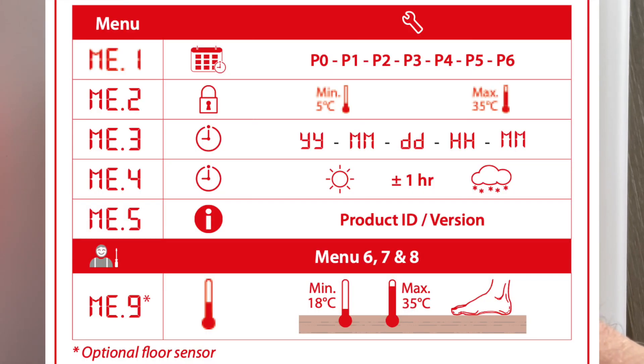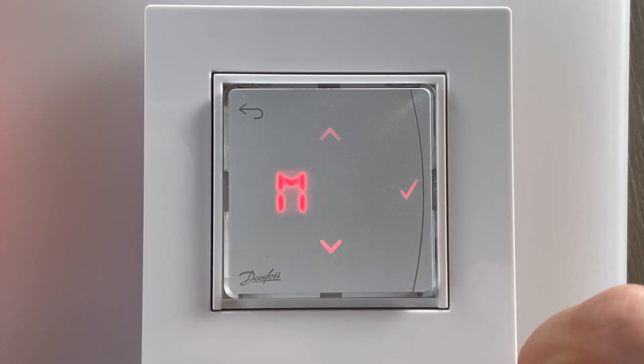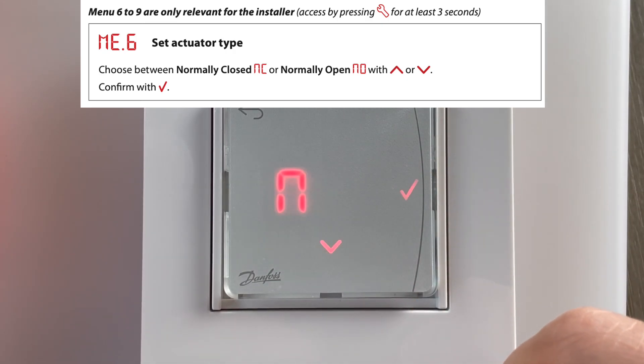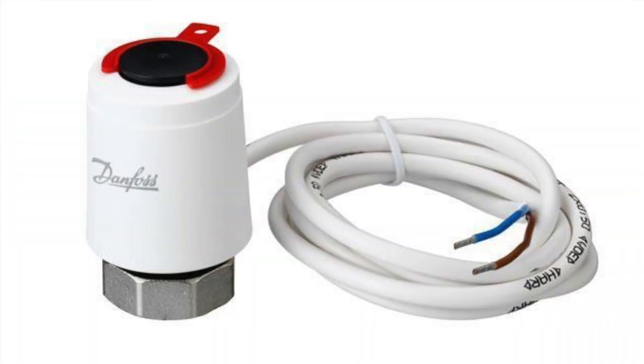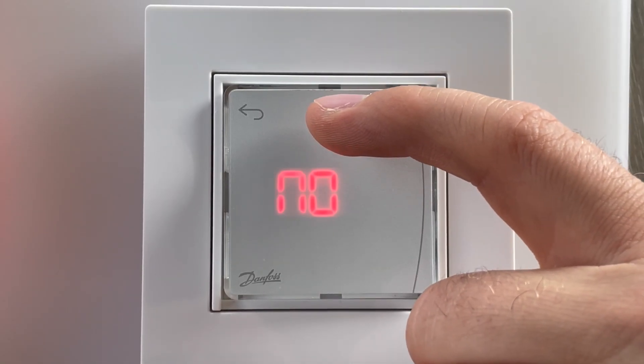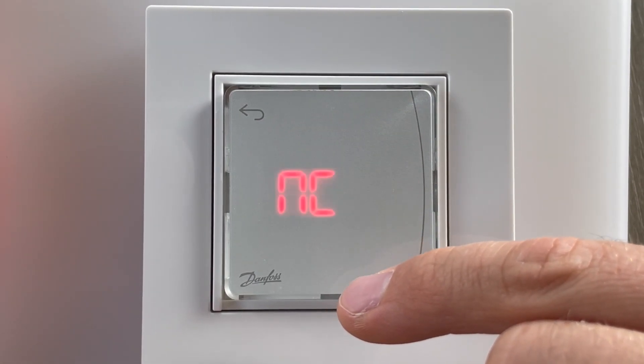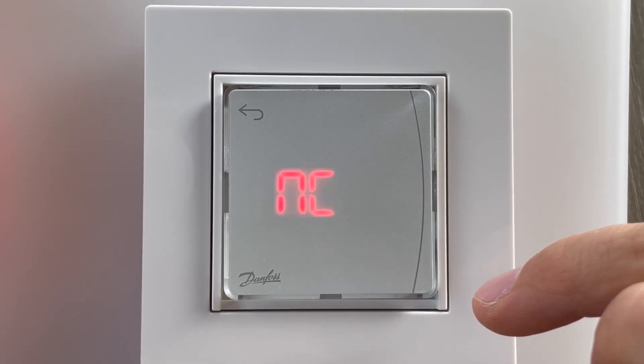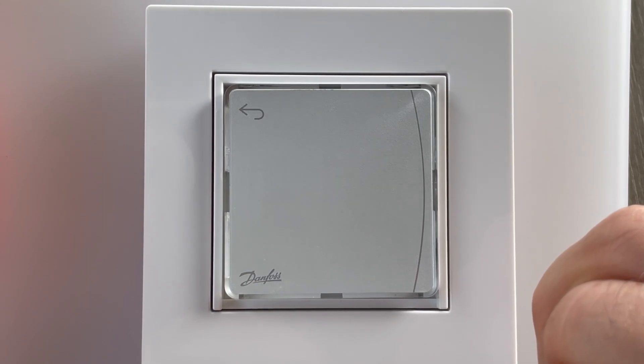You need to push and hold for six seconds to enter the installer advanced menu. Menu 6 was hidden and it is for NC or NO type actuator. When connecting the thermostat, the installer should choose the right type of actuator, which is usually written on the actuator itself. For floor heating, we usually use normally closed actuators.